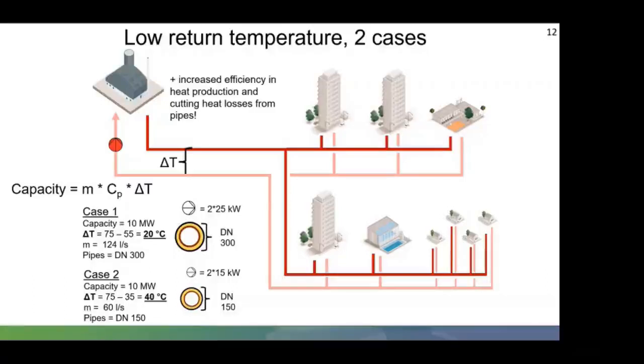So DN300 to DN150, you're the design engineers, you know exactly how much difference in price. You're talking a hell of a change when you're looking at changing pipes and valves from 300 mil down to 150 mil. Smaller pumps, smaller controls, so it's a considerable saving. Cheaper insurance, cheaper insulation. So increased efficiency in heat production, cutting heat losses from the pipes. It depends if you bury them or suspend them through the city, as they do in Berlin. Again, it's a better way of doing things, as in smaller pipework.